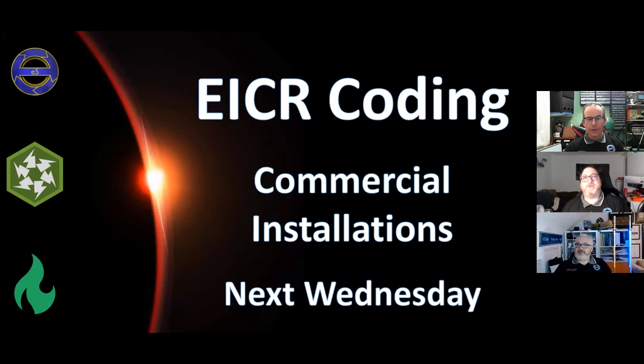Last one here from Stuart. In the AM2 exam, was it acceptable to leave a floating neutral in the Wago in the back box? I can explain why that is. It's because they gave you the wrong accessory. I have been talking to NET about this whole thing. A lot of their guidance is not correct, including their isolation procedure guidance. You should not be putting neutrals in floating connections that don't have mechanical strain retention. Just because the AM2 is managed by NET, the assessors and the centers may be getting it wrong, and they are. Shocking.